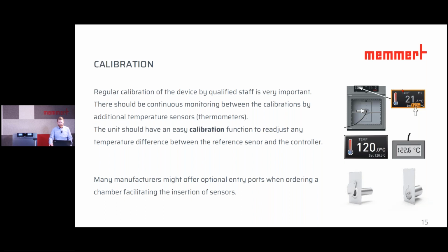The temperature display on the unit is compared with the reference sensor. If there is a deviation between the two values, the display on the unit is adapted to what the reference sensor shows and readjusted. It's important to pay attention to the accuracy of the reference sensor. It should in any case correspond to the sensor installed in the device. The unit should have an easy calibration function to readjust any temperature difference between the reference sensor and the controller. In any case, a factory calibration certificate from the manufacturer should be included in the standard scope of delivery.